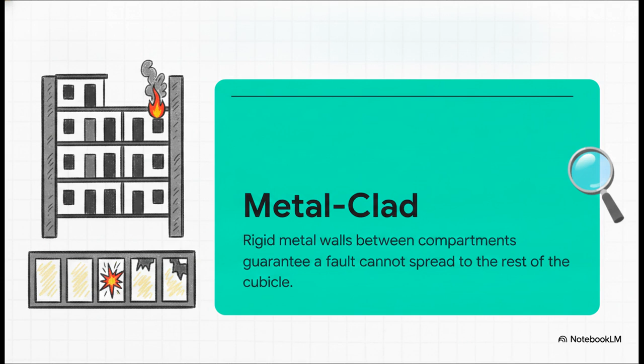Let's break down those firewalled zones really quick. Every metal-clad cubicle is built out of 5 standard physically isolated compartments. First up, you have the main bus bar compartment, which houses the raw copper bars. Second, the circuit breaker compartment holding the withdrawable breaker right on its truck. Third, the cable terminal bringing in your feeders. Fourth is the secondary equipment up top, dealing with all the delicate protection relays. And fifth is the operating unit handling manual control.